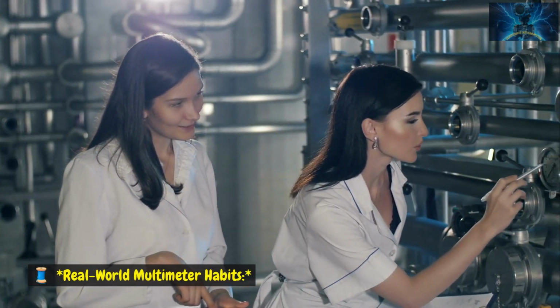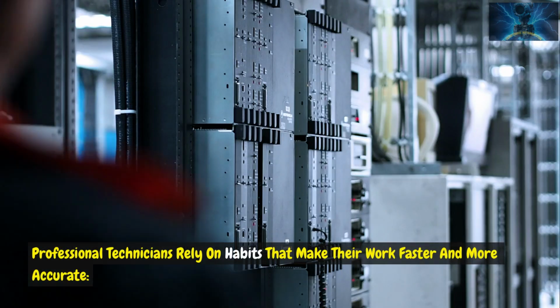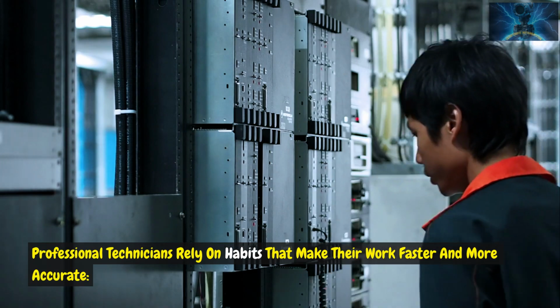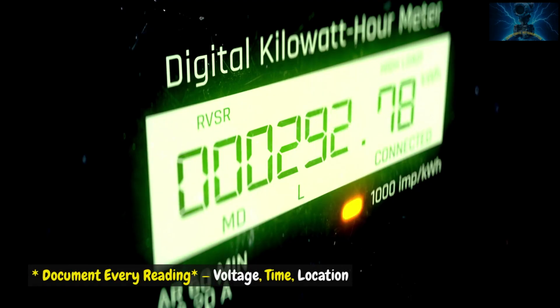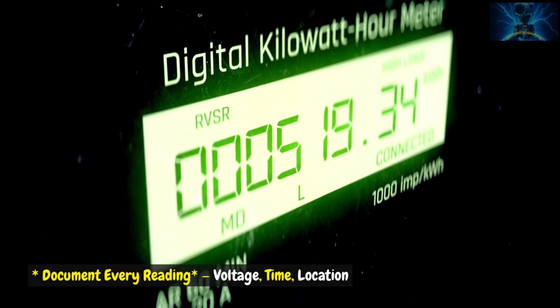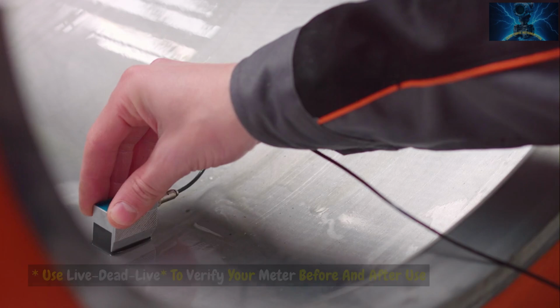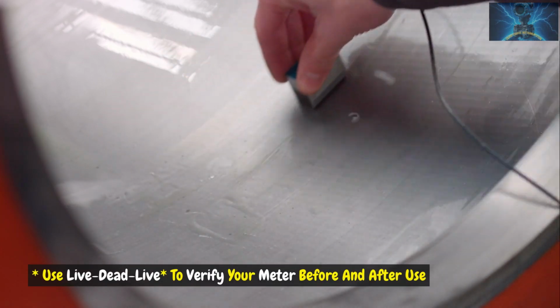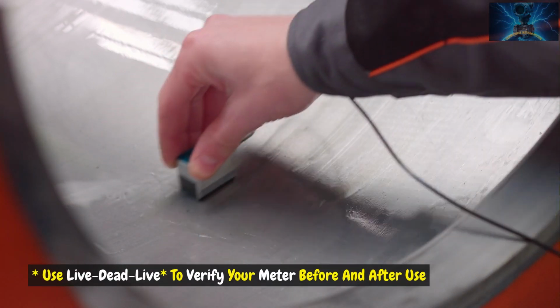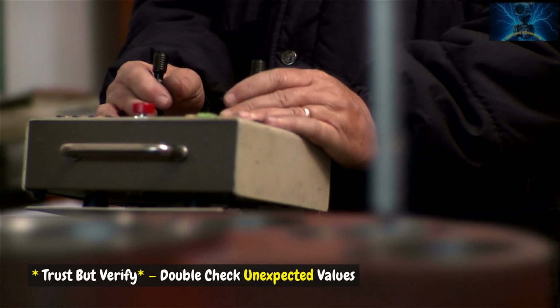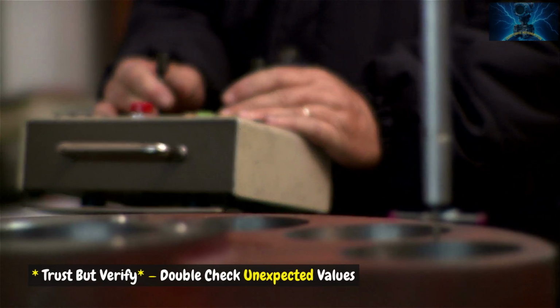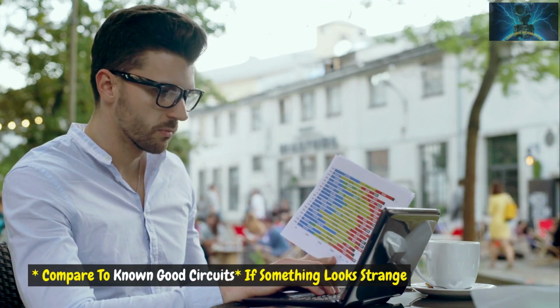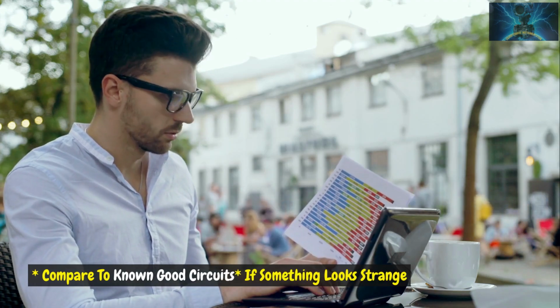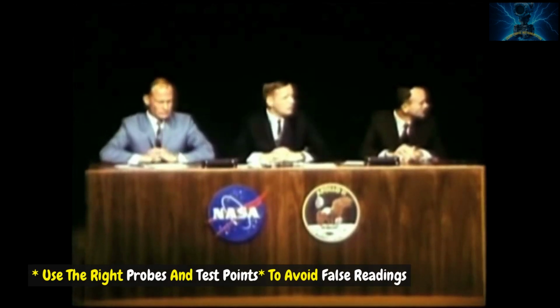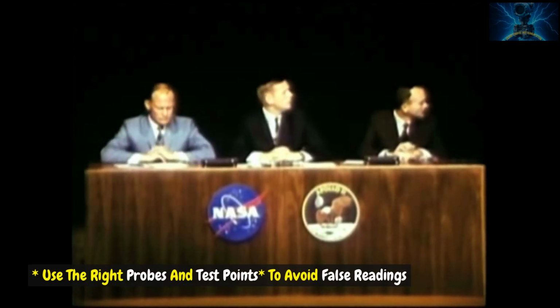Real-world multimeter habits. Professional technicians rely on habits that make their work faster and more accurate. Document every reading: voltage, time, location. Use live-dead-live to verify your meter before and after use. Trust but verify. Double-check unexpected values. Compare to known good circuits. If something looks strange, use the right probes and test points to avoid false readings.